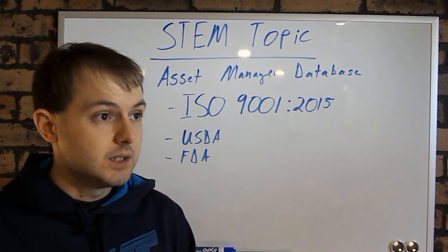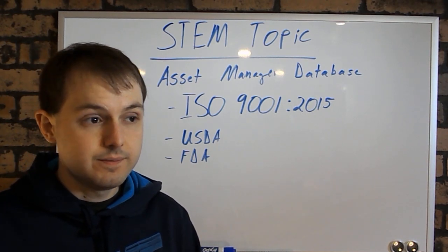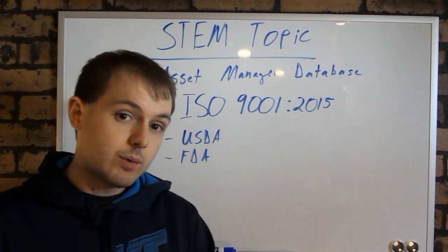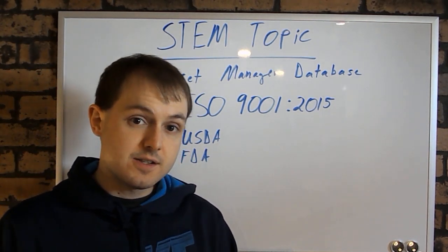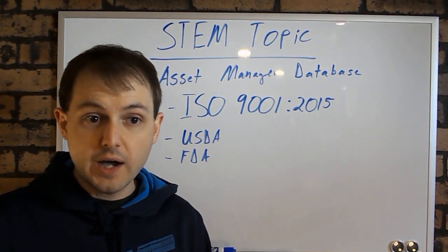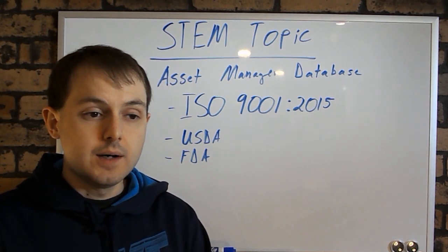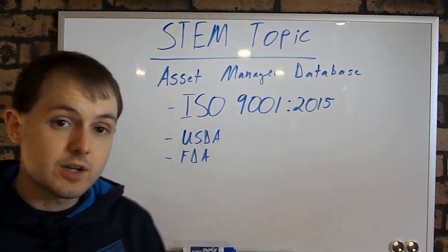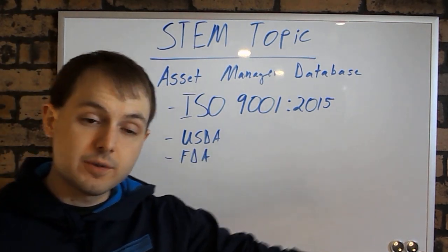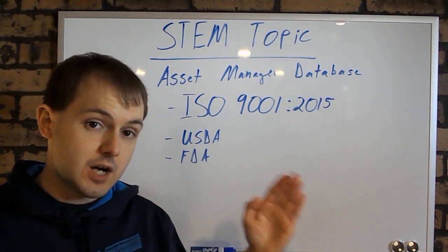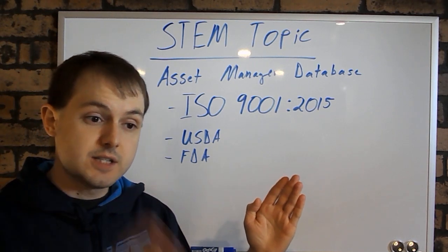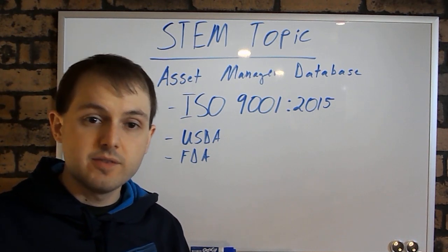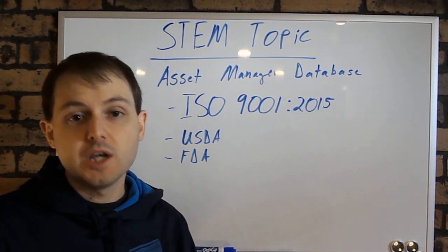They call it Asset Center, rather, is what they call it. And what I really like about Asset Center, for instance, is it has a system where it tracks it. So if you have an IIoT, so Industrial Internet of Things, or an operational technology network where your PLCs are linked together, Asset Center is going to go out, pull that information, and make sure that what it sees on your asset database system is exactly what is on your PLC, within the reason of maybe a little adjustment of a timer and some of those minor little details that can be changed in an HMI.